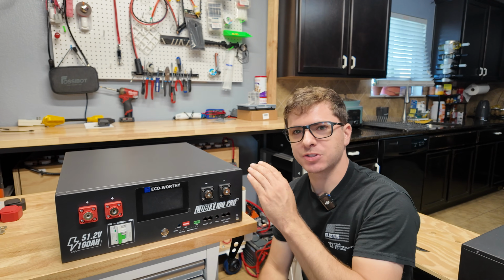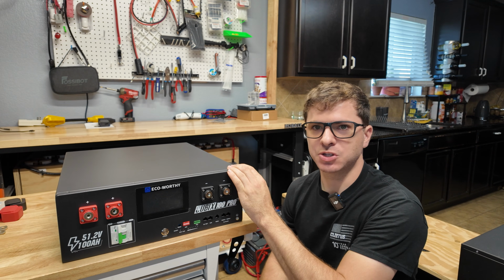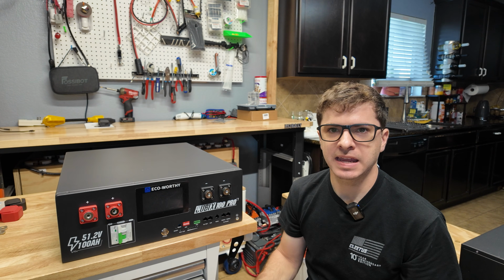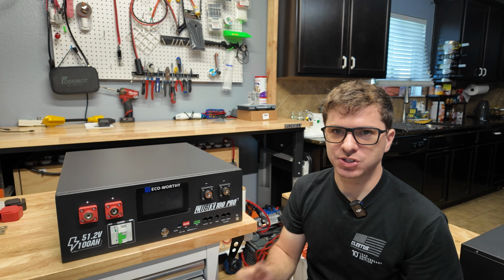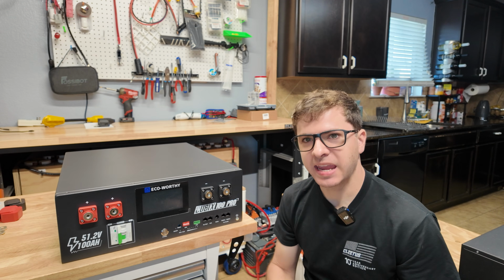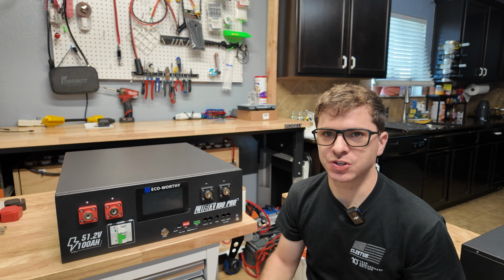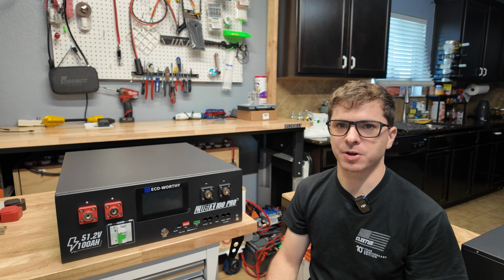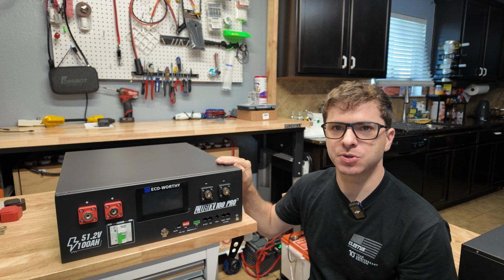But just like their standard battery, this is also rated at 100 amps continuous charge and discharge. Uses grade A lithium iron phosphate cells. They rate it to 6,000 charge and discharge cycles. It has CAN and RS-485 communication, so you can communicate with a ton of different inverters on the market. You can also parallel up to 32 of these units together.